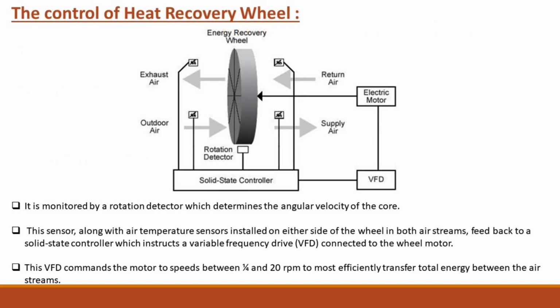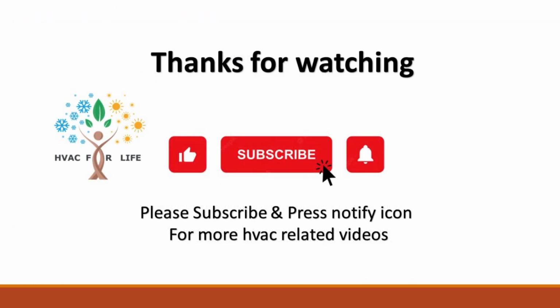The control of heat recovery wheel. It is monitored by a rotation detector which determines the angular velocity of the core. This sensor, along with air temperature sensors installed on either side of the wheel in both air streams, feed back to a solid-state controller which instructs a variable frequency drive (VFD) connected to the wheel motor. This VFD commands the motor to speeds between a quarter and 20 rpm to most efficiently transfer total energy between the air streams.